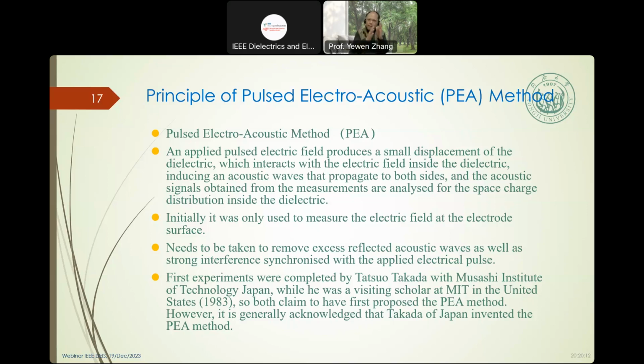So this one is electrically induced acoustic. We measure the acoustic, but measuring acoustic is not very easy. It also needs electricity. It means the electrical changes to acoustic, and changes to electrical again, so we can measure the electricity. Initially, it was only used for measuring at the electrode surface. It is necessary to remove the external reflection of the acoustic wave, as well as the strong interference synchronous with the applied voltage, because when the applied voltage pulse is applied it produces very strong noise, which is sometimes synchronous. So it's very important to separate this.